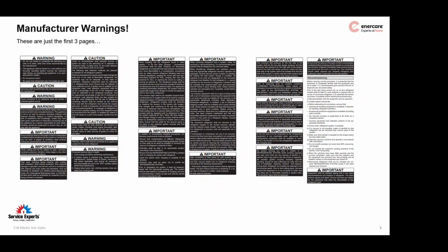They identify things that need your undivided attention, like that the refrigerant is mildly flammable, which we're already aware of. Maybe some more stringent safety practices are going to be required when installing, like making sure we're working in well-ventilated areas, preventing any possible sources of ignition, while incorporating other safe installation practices, like routing your piping, proper supports, materials. And of course, you guys are probably already doing this, but making sure we're flowing nitrogen before, after, and during brazing. Of course, having a fire extinguisher within reach. You guys know this, doing a lot of retrofit, but lockout, tag out, test out, making sure that it is electrically isolated and safe, and you're going to walk away from that job safely, especially when it comes to electricity. Things like safe refrigerant management and handling, storage.